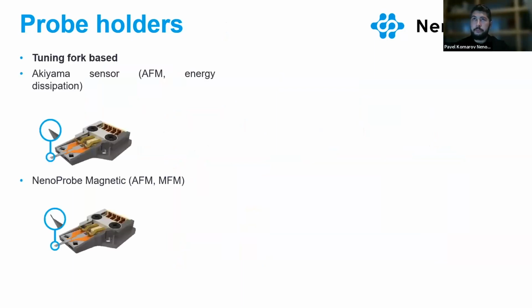Since we are measuring not only surface topography but also many other properties, we use 2 main groups of AFM probes. The first one is the Akiyama-based self-sensing probes. We are not using any laser system to navigate the AFM probe or to detect changes in the topography; the Akiyama-based probe is in tapping mode all the time, scanning the sample surface. The standard Akiyama sensor is used for topography measurement and qualitative analysis of mechanical properties. The upgraded Akiyama probe with the magnetic wire on the end is used for measurement of magnetic properties.